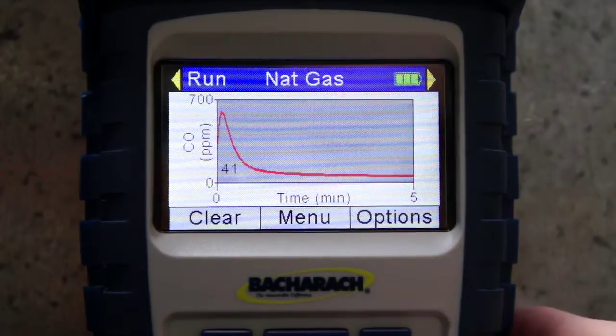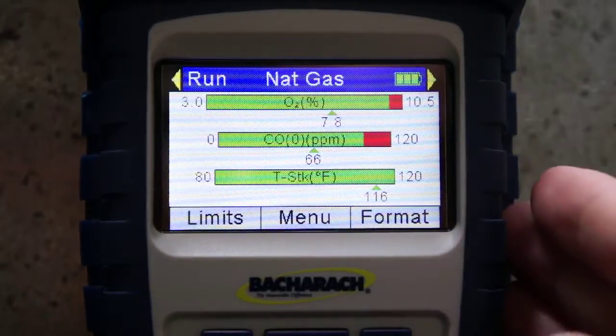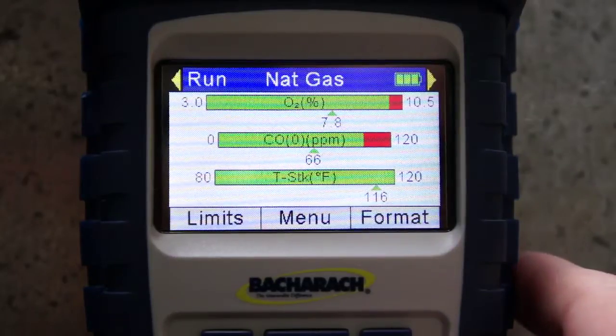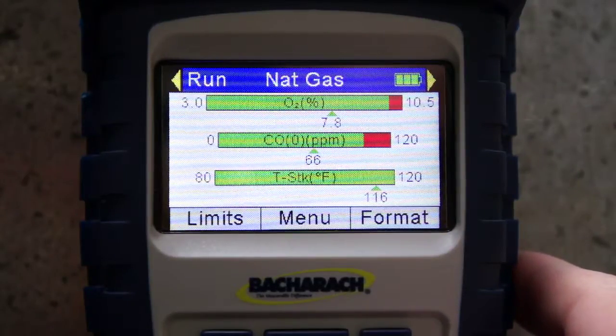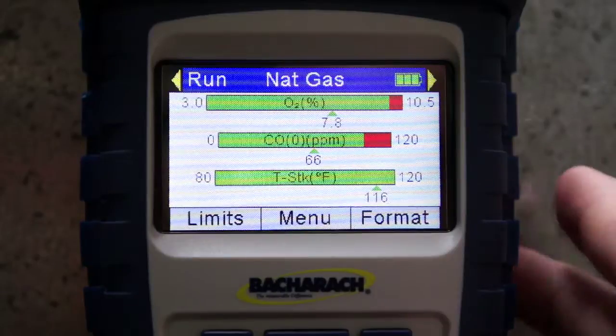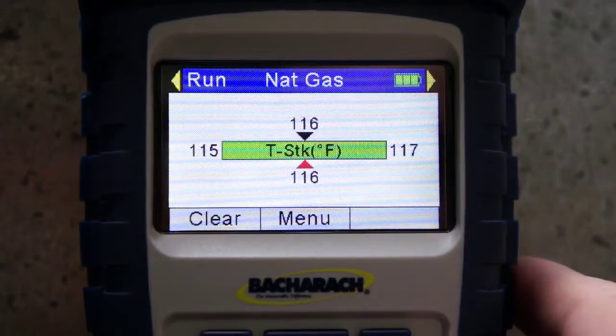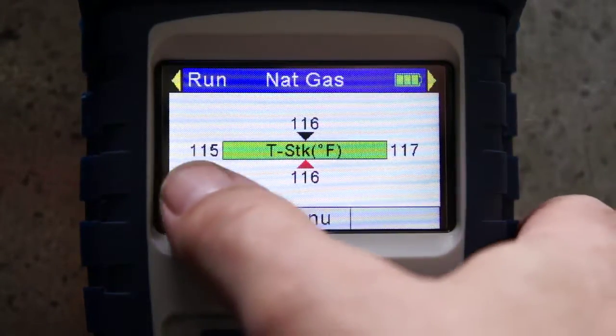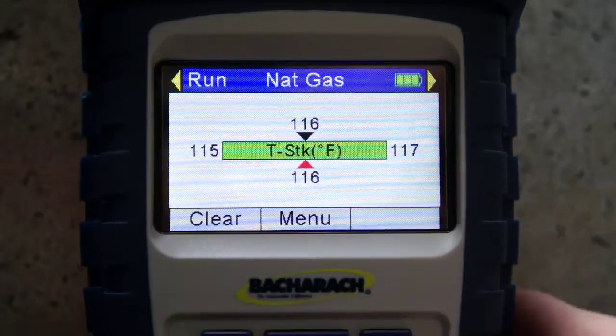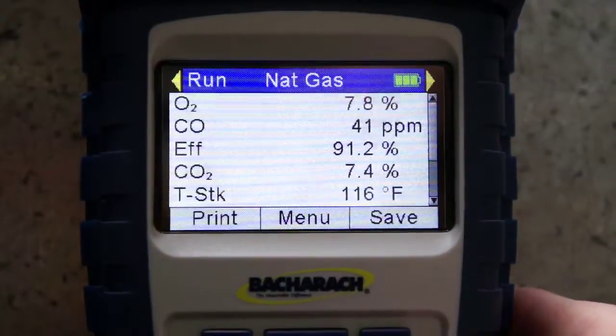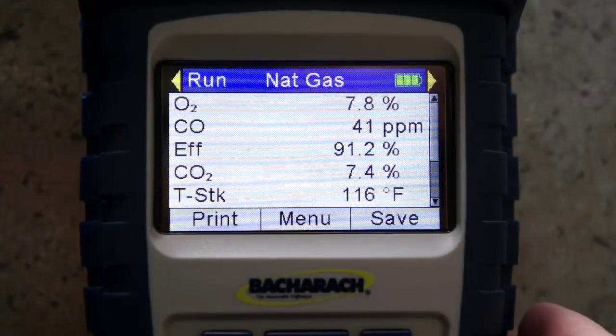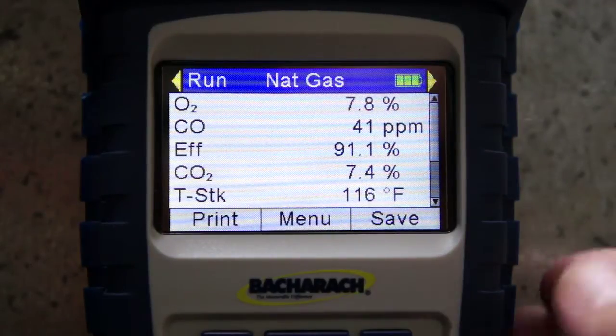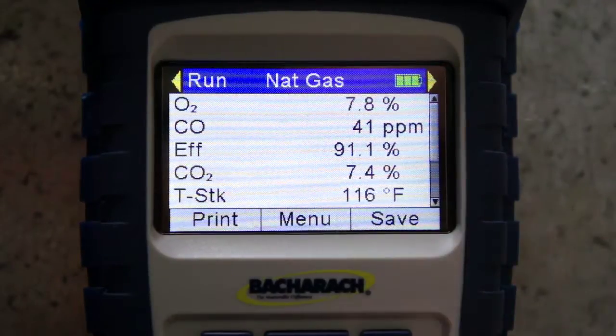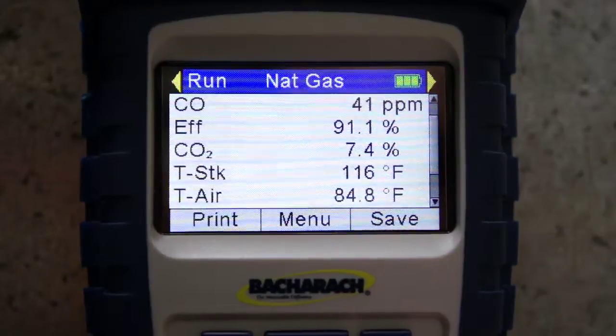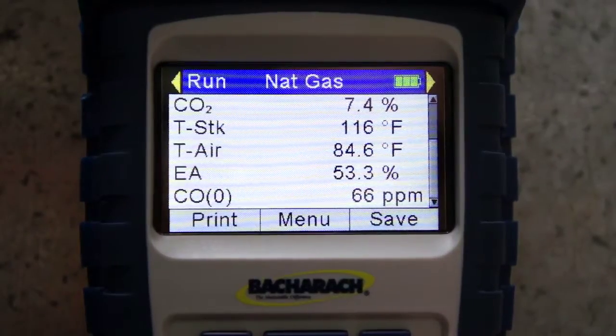You can see that's nice and steady. I can see that I'm in the green on all these things. My O2, my CO, my stack temperature, which are the three that I'm concerned with. Then I can go back in. This is my hotspot and my stack, so you can see 117 was the highest my stack temperature was. That's probably right before my blower came on. And then back to my regular menu where I can say, okay, O2, CO, whatever I want to look at, scroll through all the readings and make sure that they're where I expect them to be.